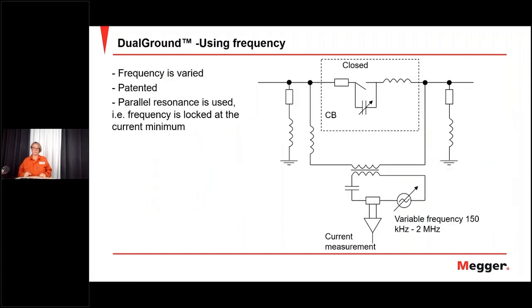Well, dual ground concept then, how does it work? Yeah, when we do normal classic timing, we work with a low voltage DC to measure whether the circuit breaker is closed or not. But when we do dual ground, we actually work with a frequency instead. So we do a resonance frequency here. So we lock the current at a certain level, and when the circuit breaker changes position, the frequency will change and the current will change.